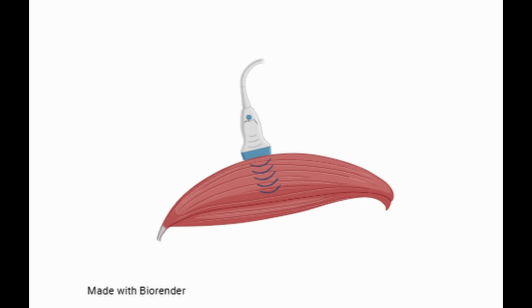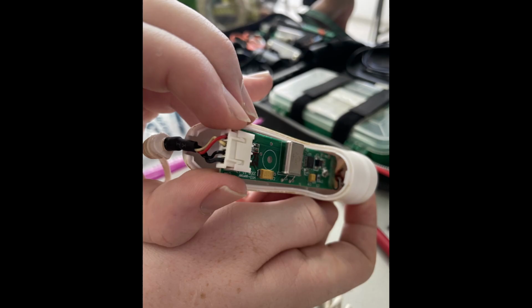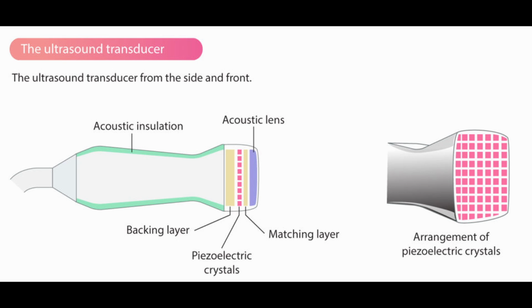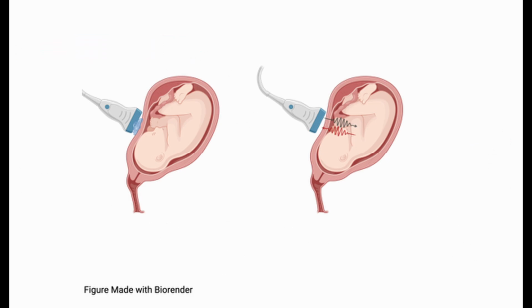Ultrasound is the use of high-frequency sound waves to extract information regarding tissue properties along the path traveled by the sound wave. An ultrasound device has in its probe a piezoelectric transducer, consisting of a special type of crystal which converts movement to electricity and vice versa. The device sends an electrical signal to the piezoelectric transducer, which then produces a specific frequency sound wave. Fetal heart monitors tend to use sound wave frequencies between 2 to 3 MHz.